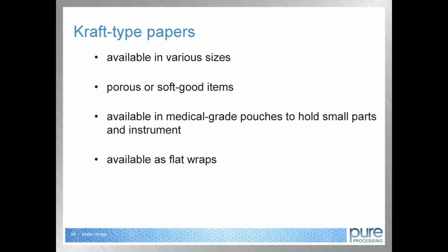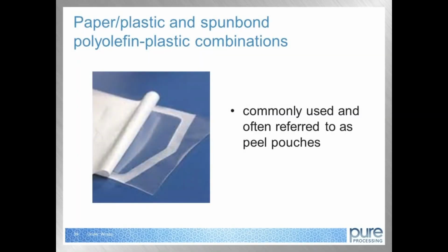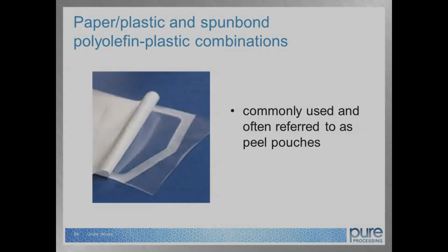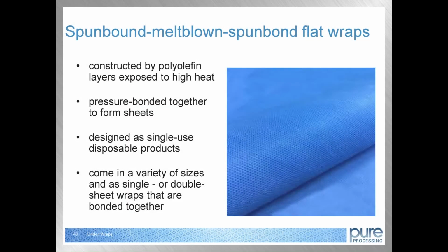Kraft-type papers are smooth-surfaced and available in various sizes and are porous or soft good items. Kraft-type paper is also available in medical-grade pouches to hold small parts and instruments. Kraft-type papers are also available as flat wraps. Paper plastic and spunbound polyolefin plastic combinations are also commonly used and often referred to as peel pouches. Spunbound-meltblown-spunbond flat wraps are widely used. They are constructed by polyolefin layers exposed to high heat and then pressure bonded together to form sheets. These are designed as single-use disposable products and come in a variety of sizes as single or double sheet wraps that are bonded together.